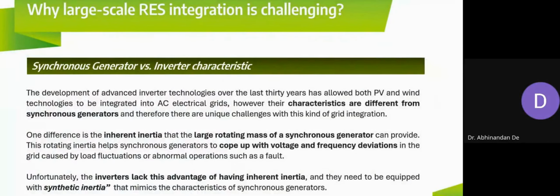So basically, as I said, this inherent inertia of the large rotating mass of a synchronous generator is quite beneficial because it can cope with voltage and frequency deviations. Inverters lack this advantage, and that is why we require some sort of synthetic inertia to mitigate the issue.